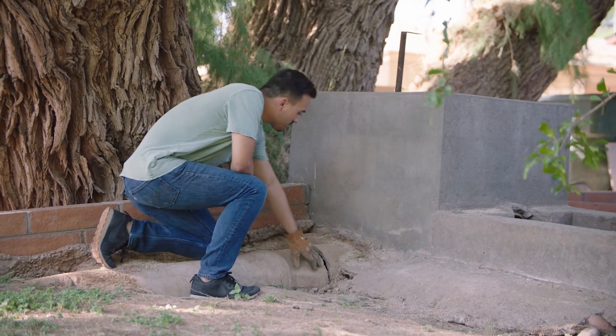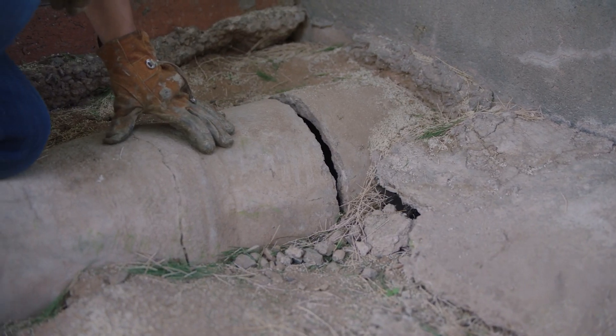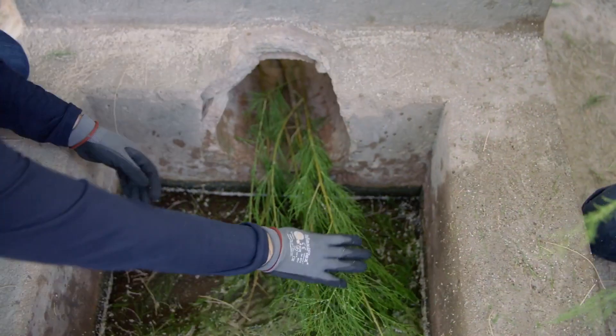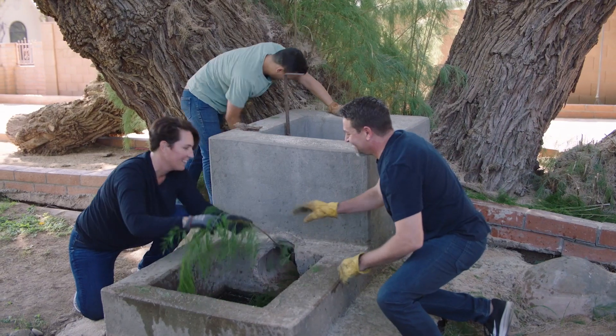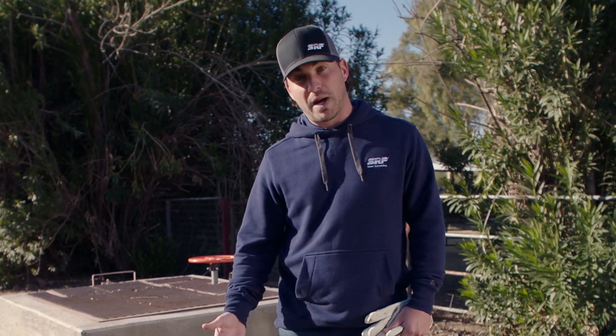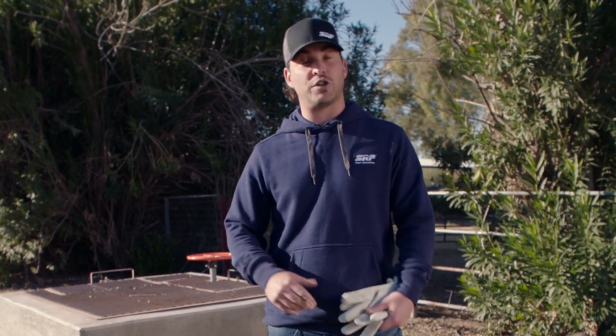When this happens, go to your nearest upstream stand box and look for any obstructions like debris — palm fronds, leaves, branches — and safely remove them if possible. Now if your water pressure still seems to be low, you might have a possible plug in the pipe system, and it very well could be a tree that has grown roots through your pipe.